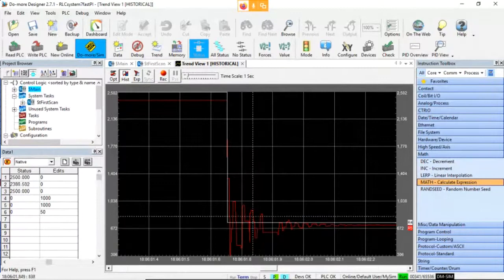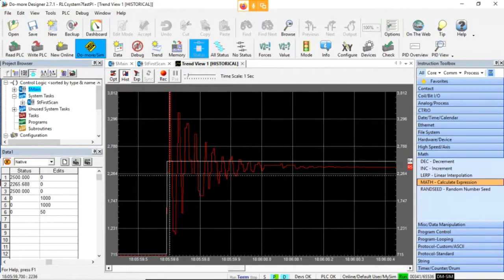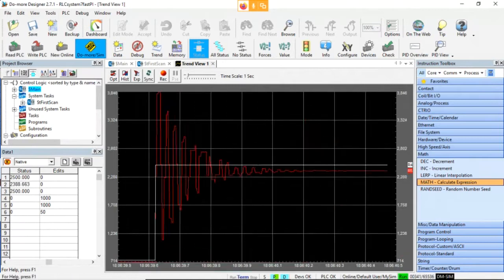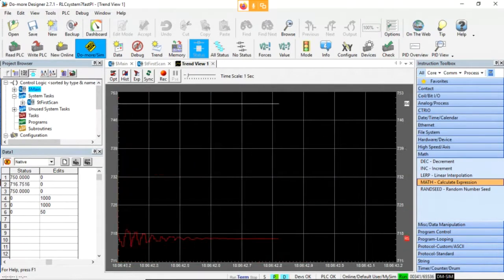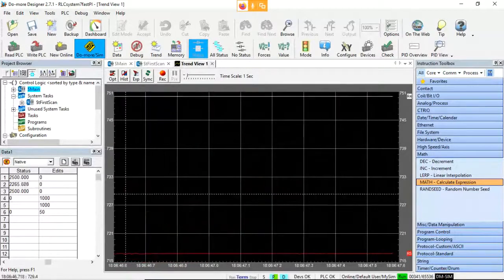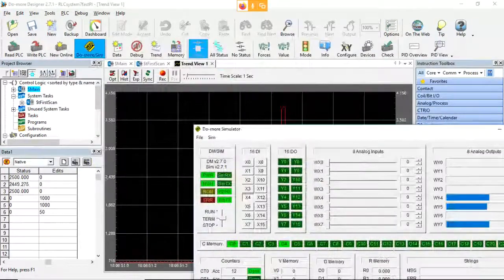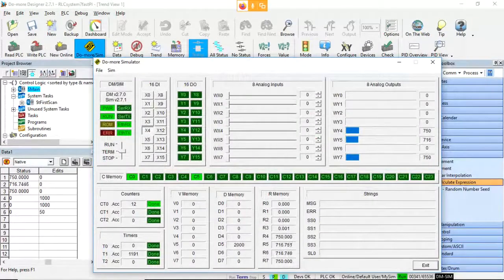You can see it just bouncing quite a bit as we look at this system. It just bounces, bounces, bounces. So this is a really, really fast system, and we want to try to slow it down. You can see these numbers bounce over here, or if we look at the simulator window, you can see it bounce when it jumps up and down. It goes real high, and then it looks like a springing action there.